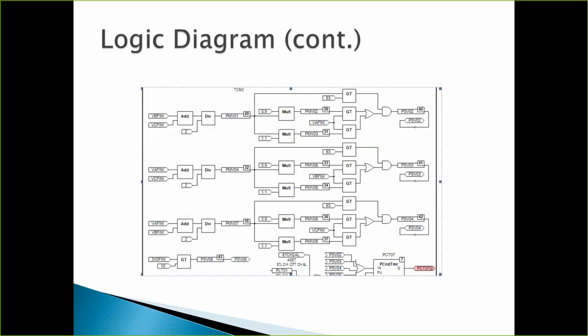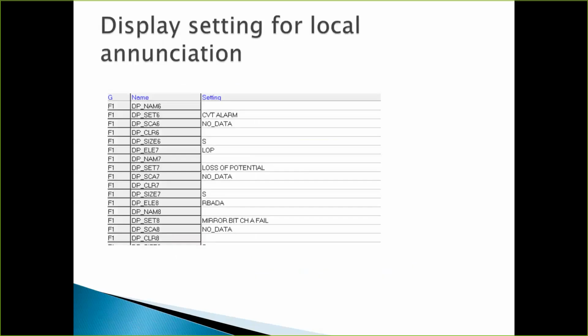I compare it to 53 volts. If it's greater than that, I satisfy the AND gate, and the same thing. So this is 3 ways of looking at the same thing. Basically, that's your logic settings. We incorporate those logic settings into the relay, and at that point, that satisfies the first part. I've got the logic settings. I've got them created. I've downloaded them in the relay. What else do I need to do?